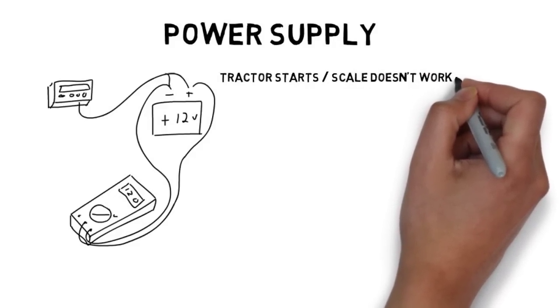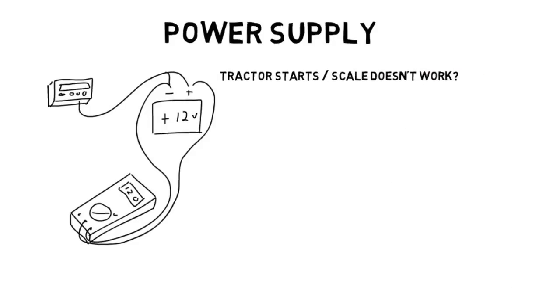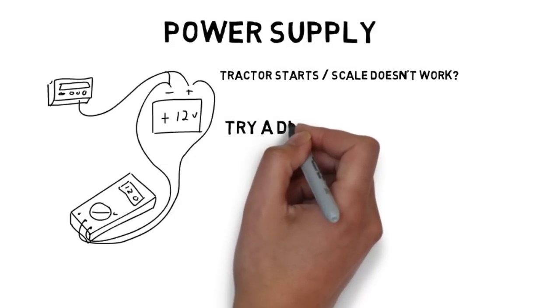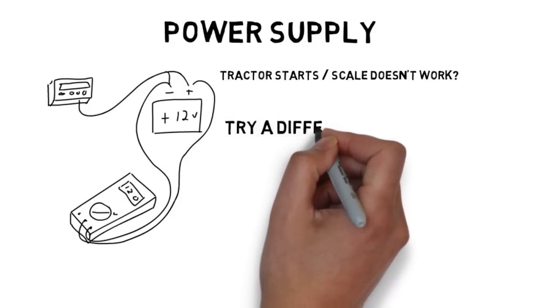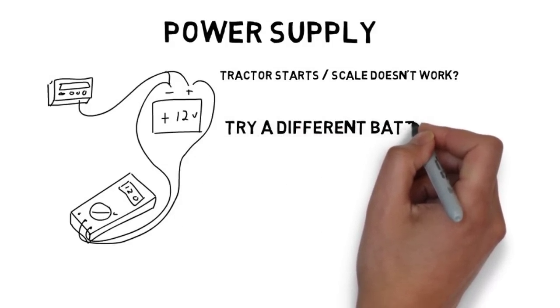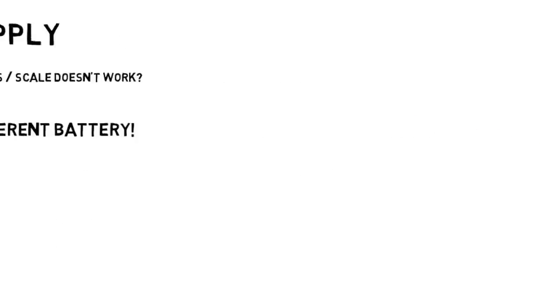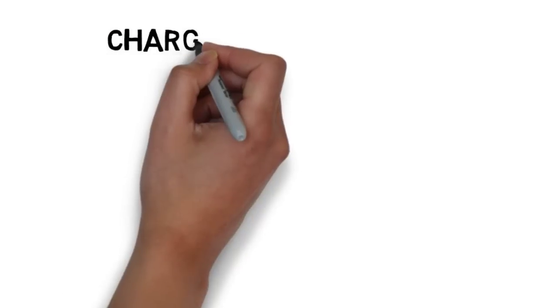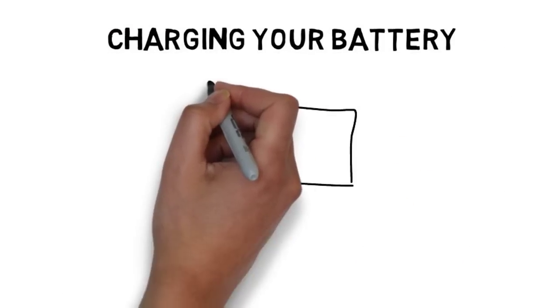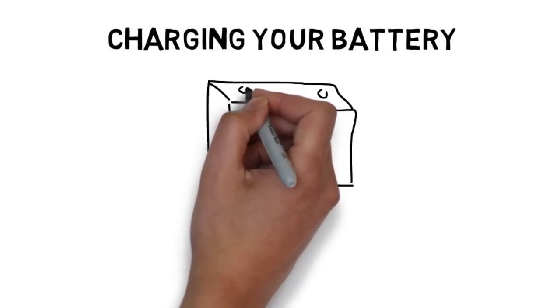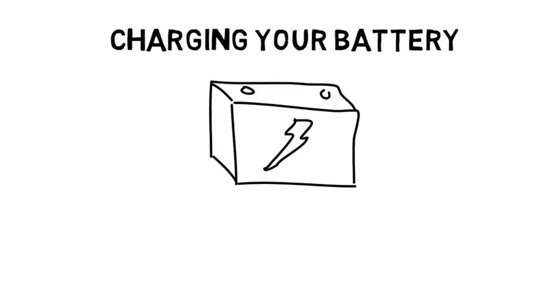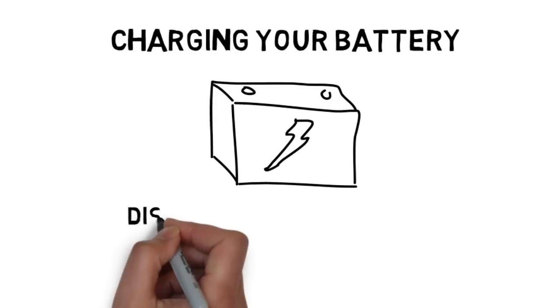Never hook your indicator directly to a battery charger. This brings up another good point. Always disconnect your power cable from your indicator while you're charging your battery. I can't say it enough. A battery charger can really damage an indicator, sometimes worse than a lightning strike.